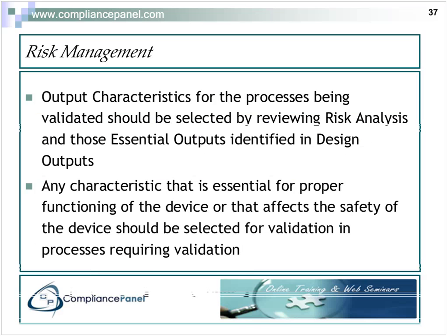Okay, risk management. That's a tool that's very important here. The output characteristics for a process being validated, one of your selection criteria could be by reviewing the risk analysis and looking for those items that were identified as risk control measures and those essential outputs identified in design output.